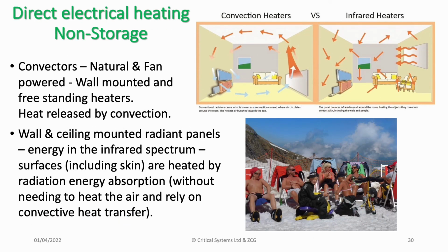Now I want to look at direct electrical heating, non-storage. And there are two options available for such an approach. So convection devices or infrared devices. So convectors, natural and fan powered, could be wall mounted or freestanding. And here, in the diagram on the left, the heat is released from the device and it heats the space, the air in the space.